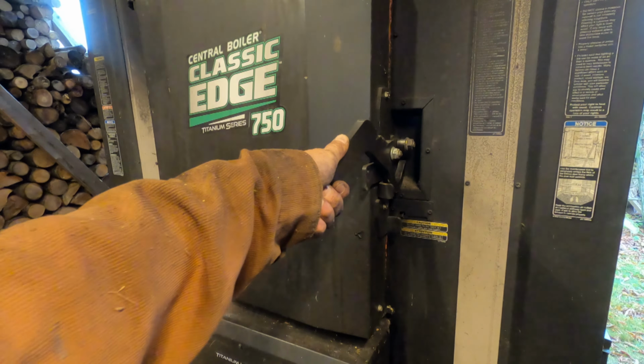So with a lot of heat now going through the heat exchanger in the back, I'm going to plug the circulator in, a larger one, and that'll circulate it through the house heat exchanger and back, but also in the tank here to make sure the heat that's going to the water by the heat exchanger is circulated everywhere. I'm not sure it'll do much to that temperature. It might drop it momentarily before it heads back up again.